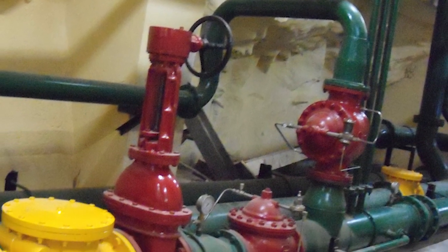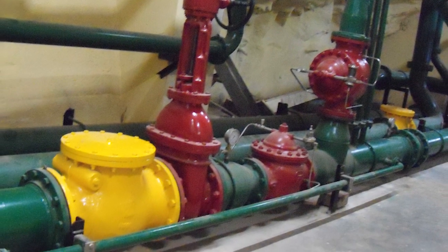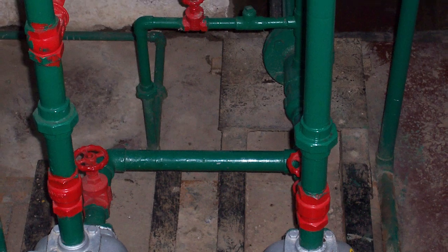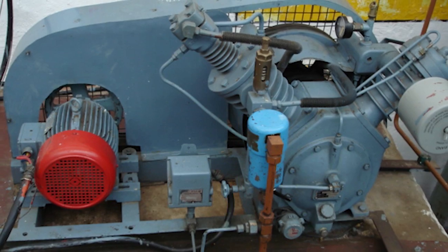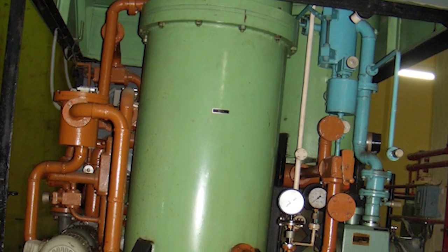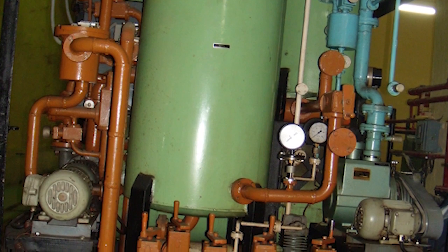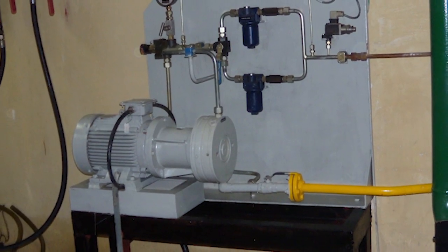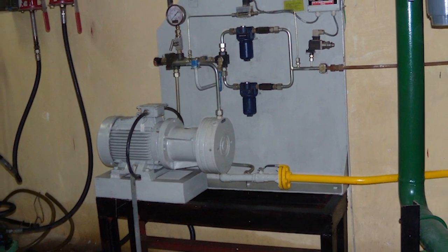Cooling water system. The cooling water system is designed to meet the cooling water requirement of equipment in the powerhouse, such as generator, bearings, transformer, OPUs, etc. Low pressure compressed air system. It is used for generator braking and jacking. High pressure compressed air system. It is used for supplying compressed air as emergency backup for operating OPU valves during AC power failure. Turbine lube oil plant is used for lubrication of turbine guide bearing.